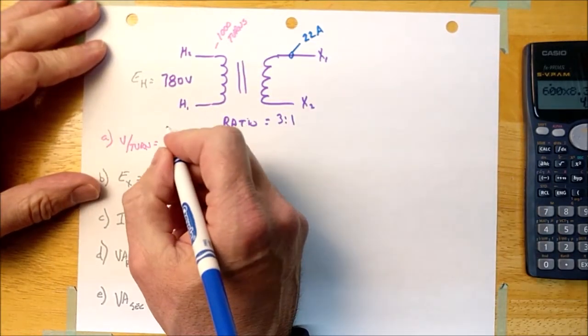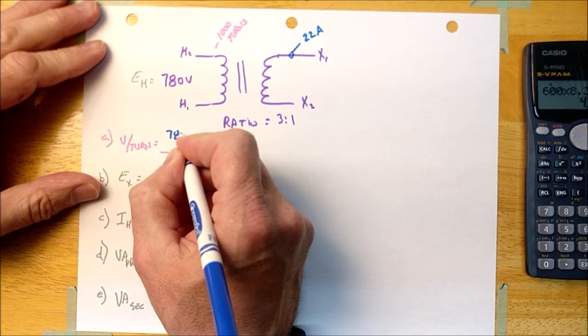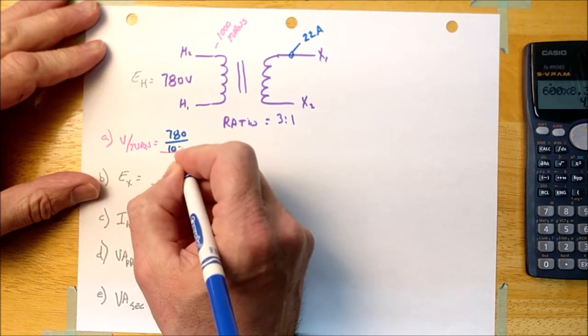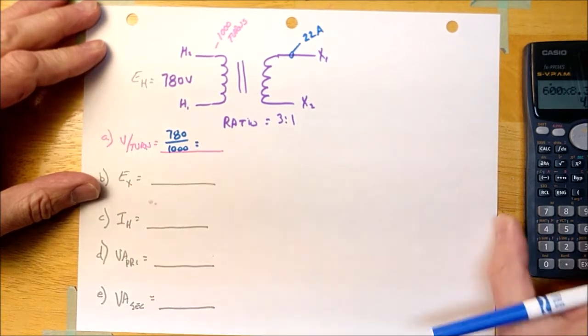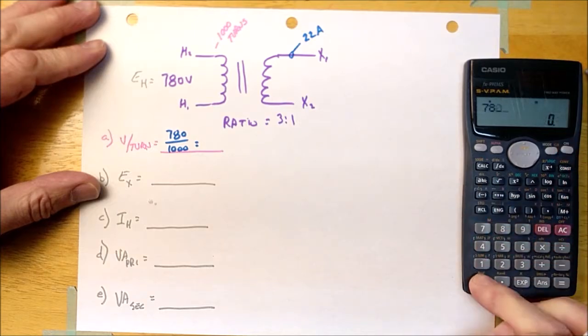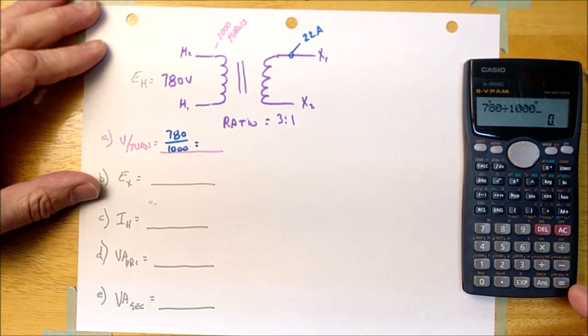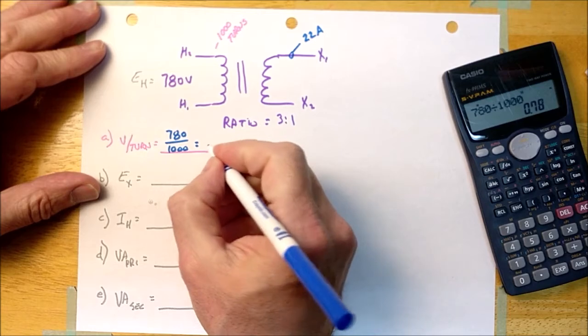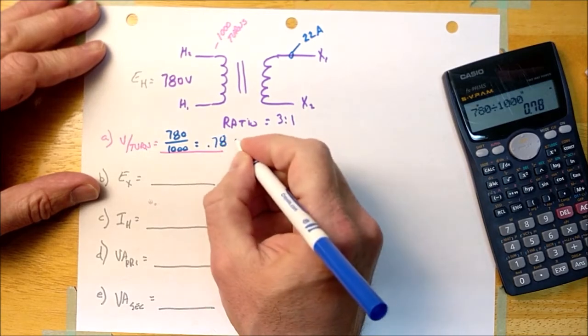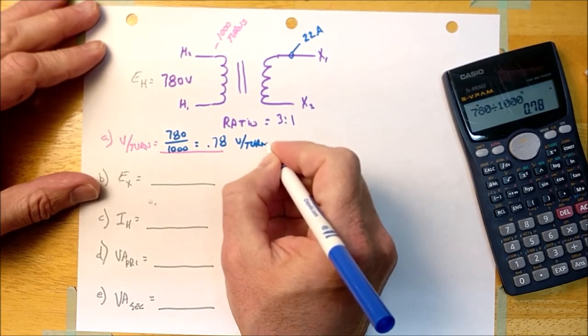The voltage per turn, we're going to use the 780, guys, over the 1,000. It looks like it's 0.78. 780 divided by 1,000, yeah, it's 0.78 volts per turn. Okay, guys, and that's good.